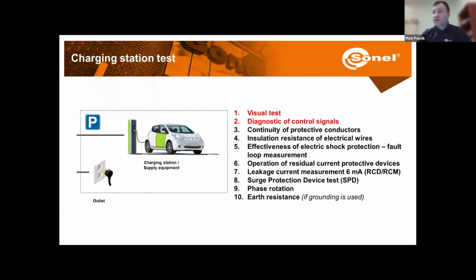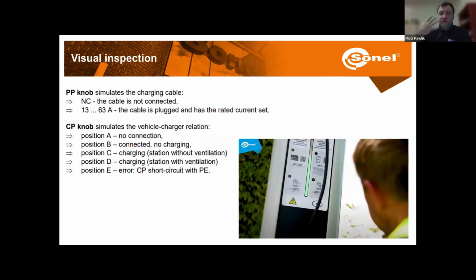And now let's see all of the measurements that we need to perform, of course, the applicable ones to the appropriate charging modes. So first, we are going to do the visual test and diagnostic of control signals. With the visual test, we are going to check with our eyes and appropriate senses if all the equipment is installed properly and there are no loose connections. There's also a big list of different elements, not necessarily connected with the electrical part, but to check, for example, the protection of the cover of the entire station to make sure that there is no water inside. There should be some barriers preventing cars from driving onto the station. We don't want to hit it with the car, and so on. But yeah, there's a whole list.